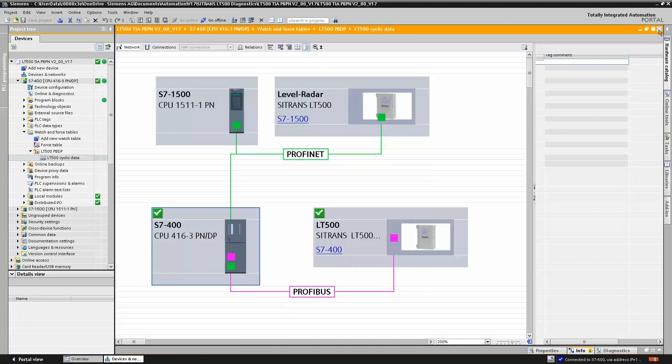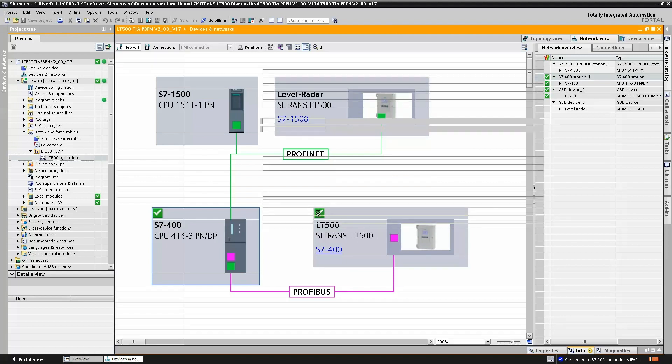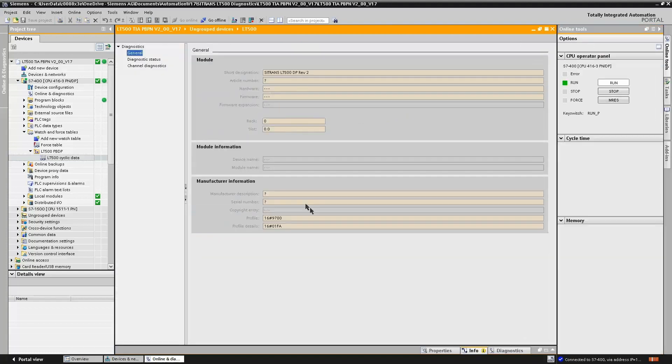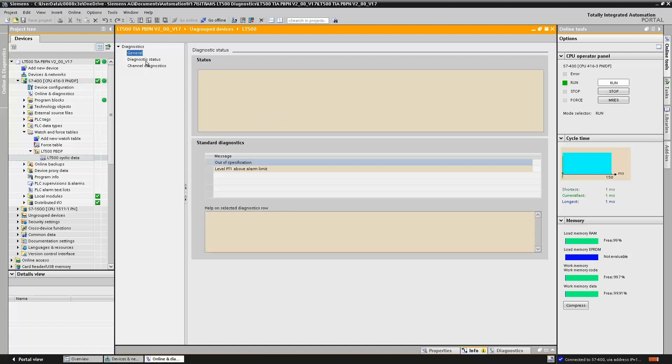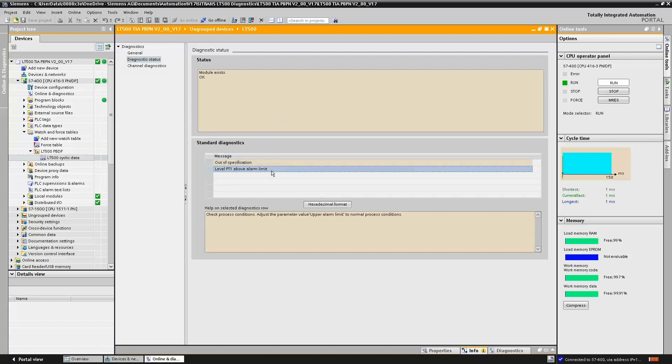Well, because the Sitrans LT500 conforms to PA Profile 4, alarm events such as process alarms and diagnostic alarms are handled separately. If we go online to the Sitrans LT500, we'll see we do have an alarm event, but it's just a high alarm limit.